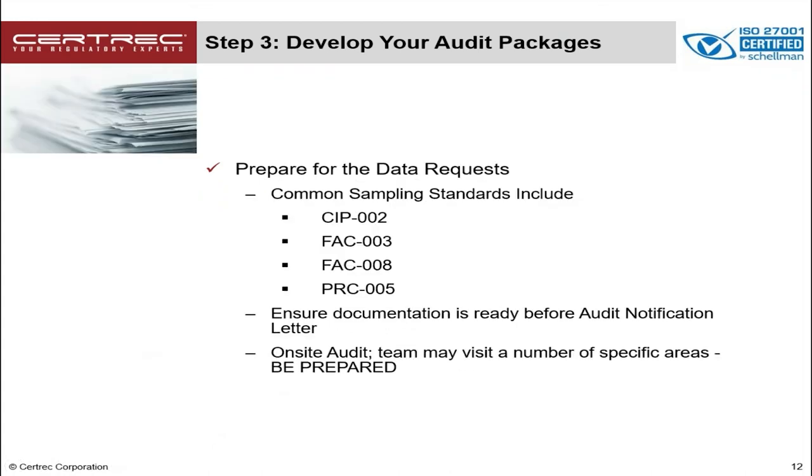Step 3 also includes preparing for any data requests. You can be assured that every audit will include the initial request for your CIP-002 BES assets, as well as PRC-5 protection system equipment list with maintenance and test records, and your FAC-8 BES facilities and their associated ratings — those are always going to be included. We highly recommend that you get these prepared before you receive your audit notification letter because you're not going to have a lot of time. When you get that audit notification letter and those templates, you can simply copy and paste those into the regional or NERC templates that come in the notification package. Don't wait until the last minute.